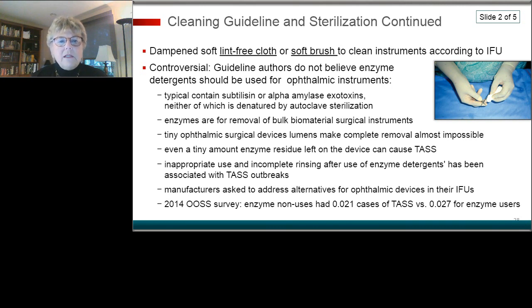Guideline authors do not believe that enzyme detergent should be used for ophthalmic instruments. This is from the guideline. In some cases, if you had excellent rinsing and removal of the enzyme, it would not be an issue, and it was helpful. But what they're explaining is that enzymes are more for the bulk organics, with the viscoelastic and things like that in there. Very often the contamination are things that will dry on and things that will cause a problem, but aren't necessarily at high organic content. The enzymes that remove bulk normally in surgical instruments, which is extremely important, I believe, in using enzymes there.